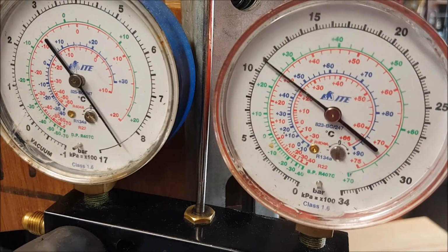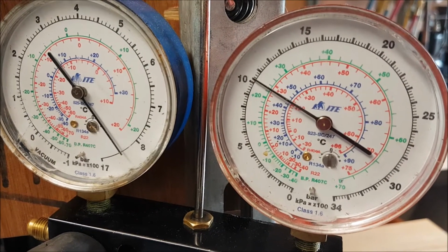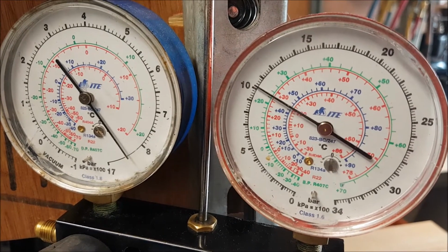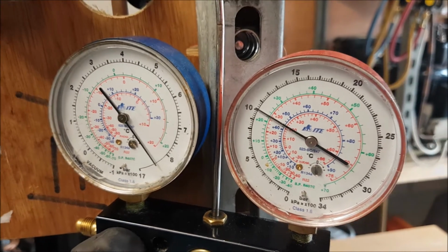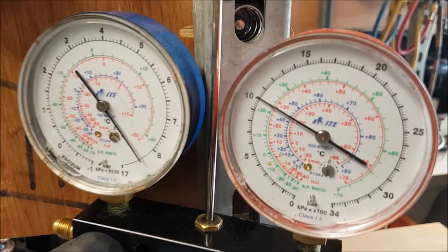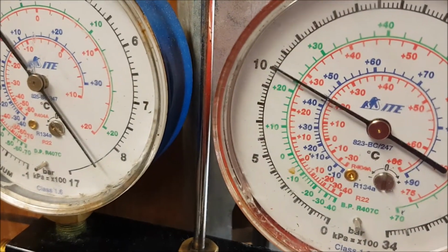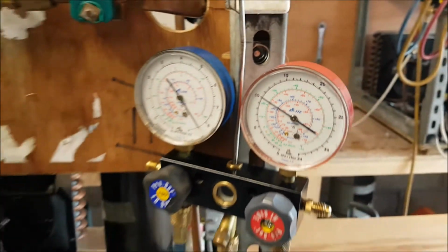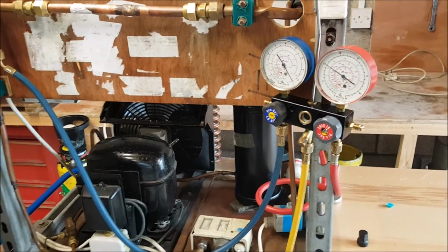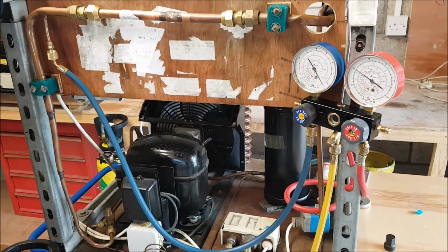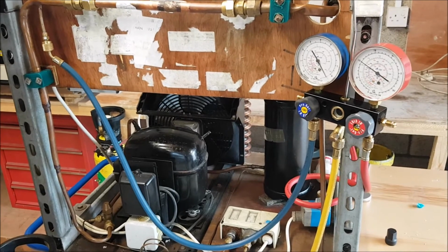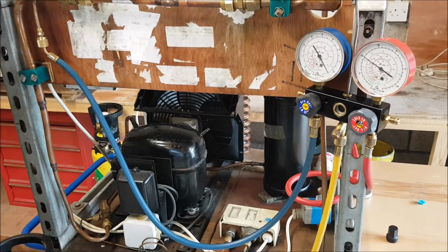So what I would recommend at this point is that you leave that for as long as possible after you've gone through. You've gone with your 10 bar, you've gone through with your bubble solution, you've checked it with your eyes, you've checked it with your ears. So you go through the whole system and you satisfy yourself that that system is leak free. At 10 bar pressure, the longer you leave that there, the better chance you can see if there is any kind of subtle leak.